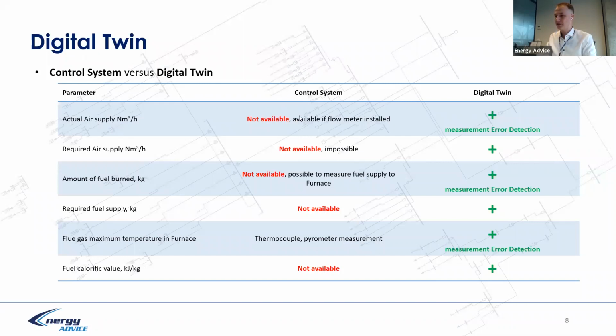And even if we have an installed meter device, we can check the measurement error, detect the error, or see what the error is between the measurement and the calculated value. It's like a calibration or monitoring of precision. We can calculate the required air supply for the boiler, for the burning process. In fact, in the control system it is not available and probably not possible, because we need mathematics describing the burning process, but in the digital twin we definitely have it.